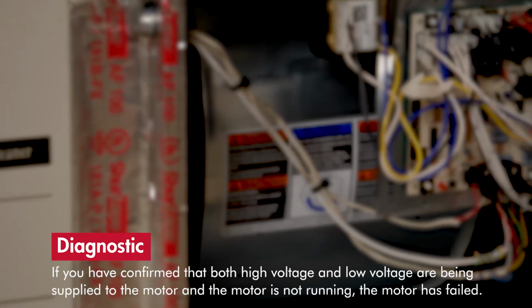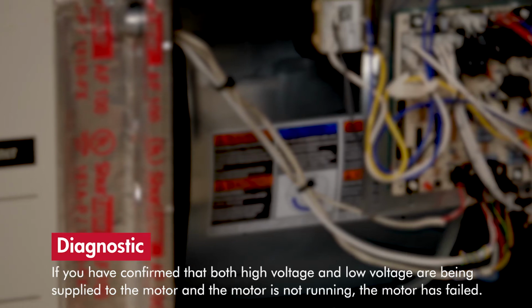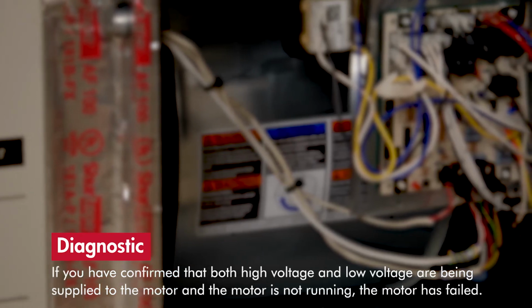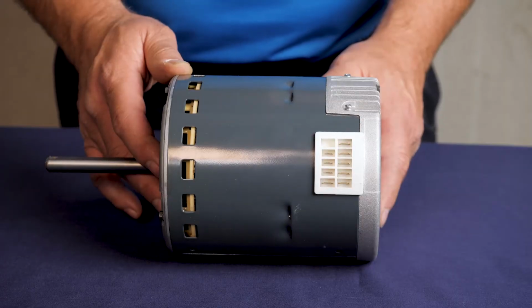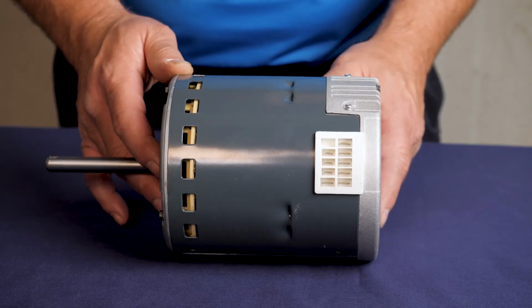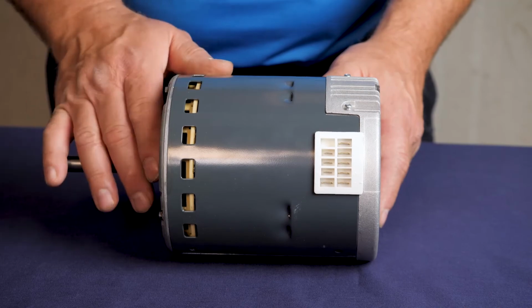If you have confirmed that both high voltage and low voltage are being supplied to the motor and the motor is not running, the motor has failed. The constant torque X13 style motor is a one-piece motor and will have to be replaced.